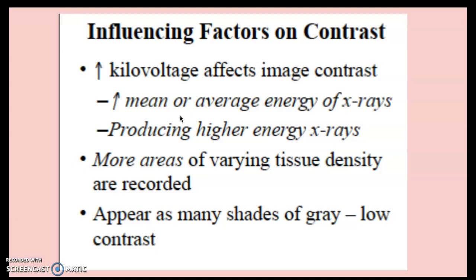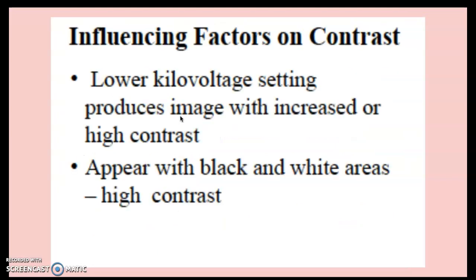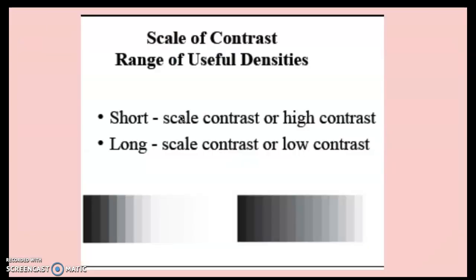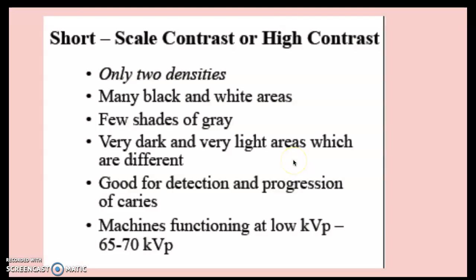Higher kilovoltage produces images that appear as many shades of gray, which is low contrast. Lower kilovoltage settings produce high contrast — more black and white areas. There is a short scale and a long scale of contrast. The short scale has high contrast; the long scale shows low contrast. The short scale has only a few densities — many black and white areas, very few shades of gray. It's good for detection of caries and the machine functions at low kVp, 65 to 70.